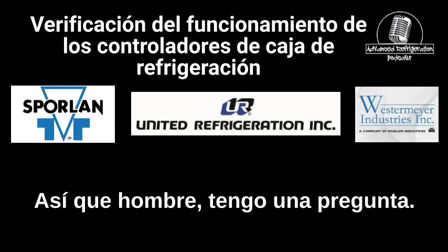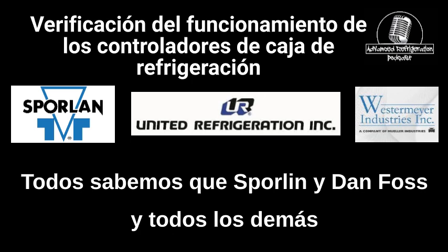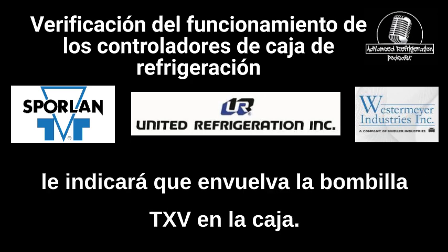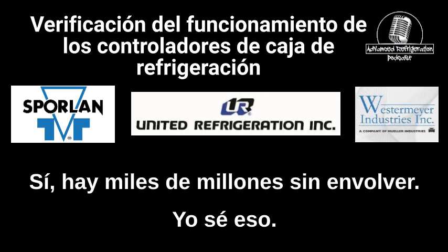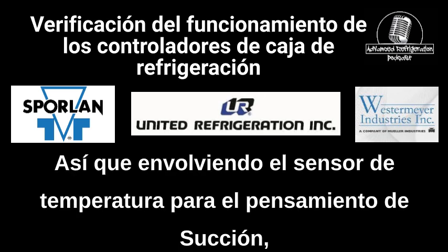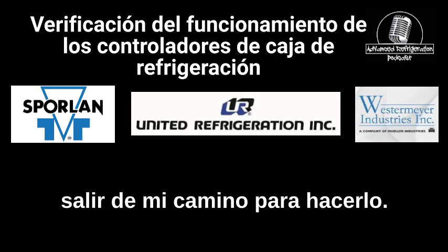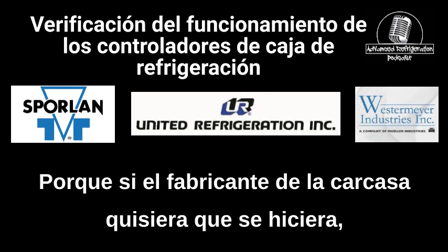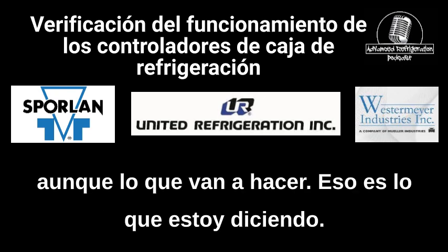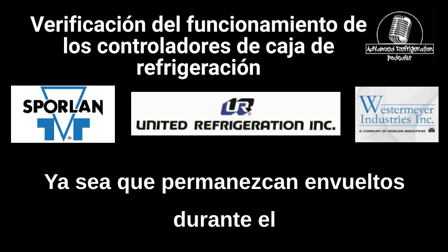Go ahead, Brett. So I have a question. What is your protocol? We all know that Sporlan and Danfoss and everyone else will tell you to wrap the TXV bulb in the case. There are billions unwrapped, I know that. So, wrapping the temperature sensor for the suction, thoughts? I think it should be done, but I'm not going to go out of my way to do it. Why not? Because if the case manufacturer wanted it done, they would have done it, because they know what they're doing. A lot of them do, though. That's what I'm saying. A lot of the ones I have been seeing have them wrapped. Whether they stay wrapped during the shipping process, that's another story.